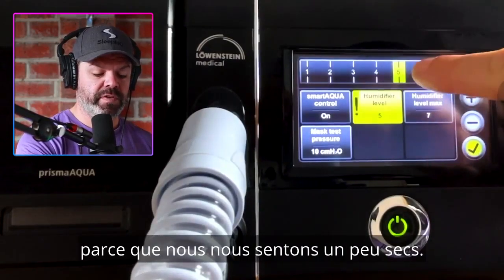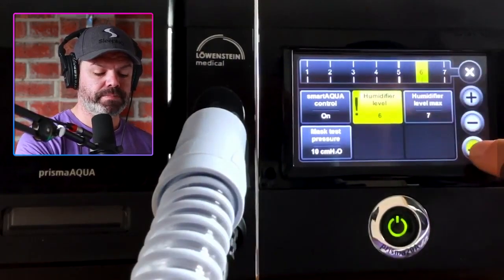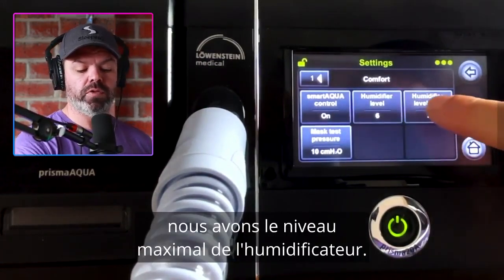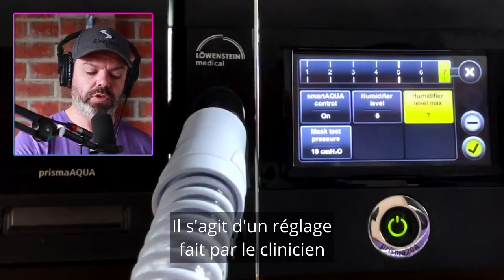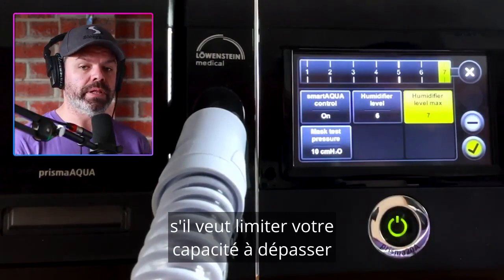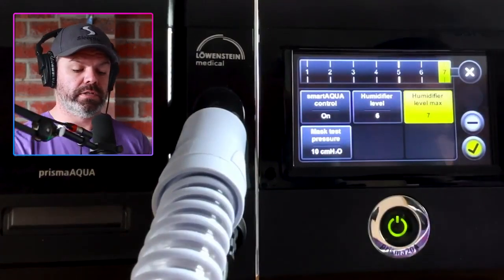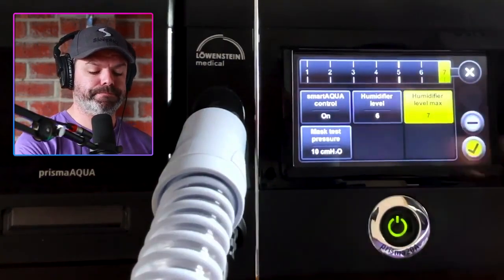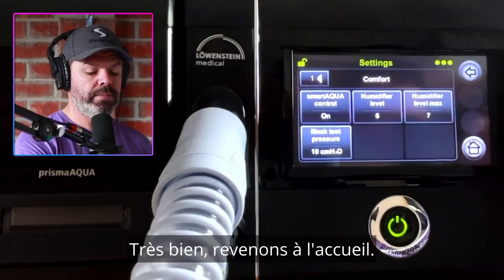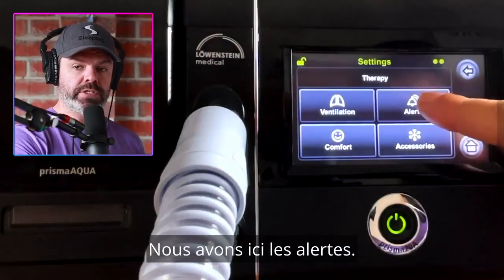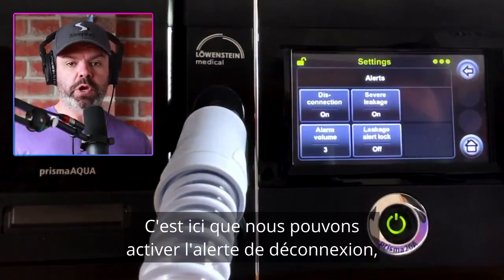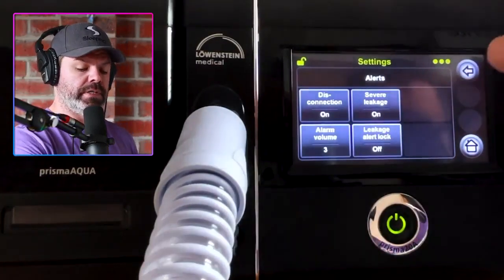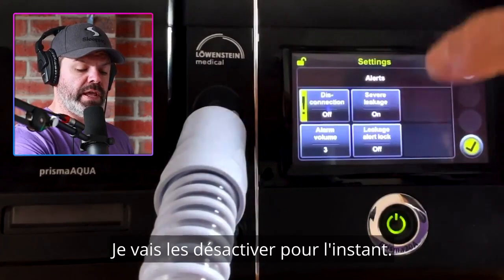We'll increase the humidifier level because we're feeling a little dry. We also have a humidifier level max — a clinician control that limits your ability to go above a set humidification level. We want that set to seven. Under alerts, we can turn on the disconnection alert and the severe leakage alert. I'm going to have them off for now.